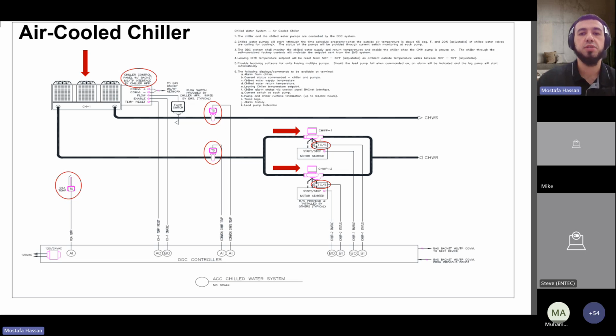The leaving chilled water temperature set point, leaving the chiller, will be reset from a certain range of temperature, 50 degrees to 60 degrees, and that's adjustable as ambient outside air temperature varies between 80 degrees and 70 degrees. You don't have to remember these exact values, but I'm just trying to help you build the sequence of operations in the space.